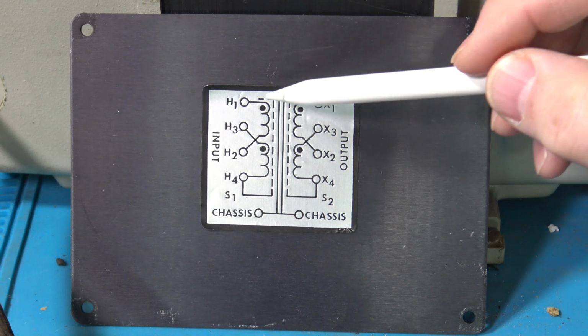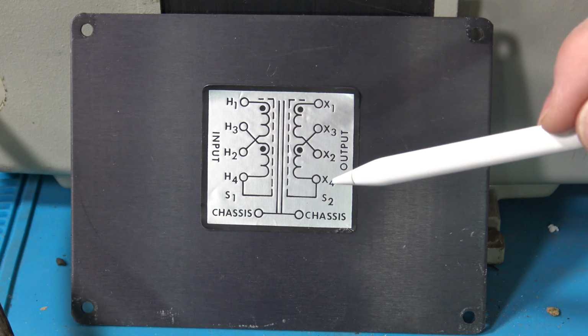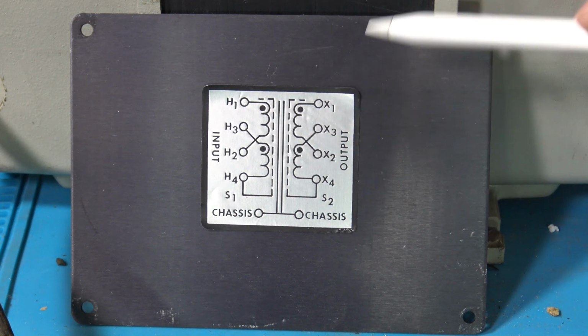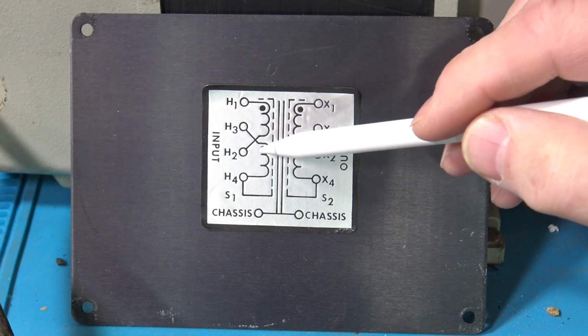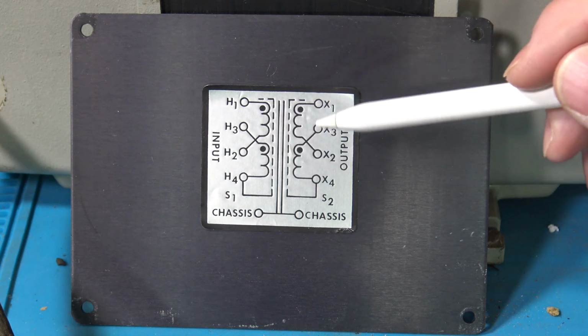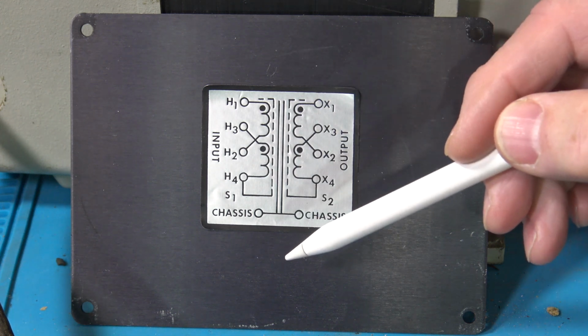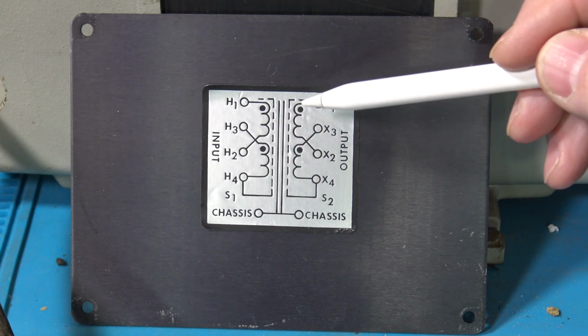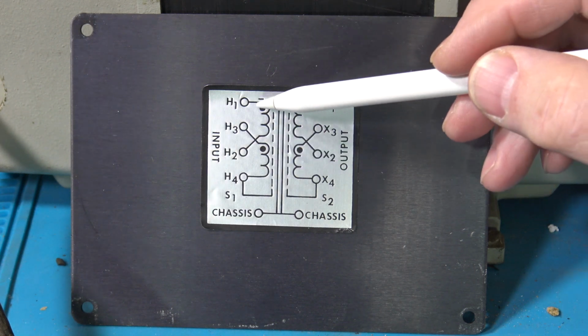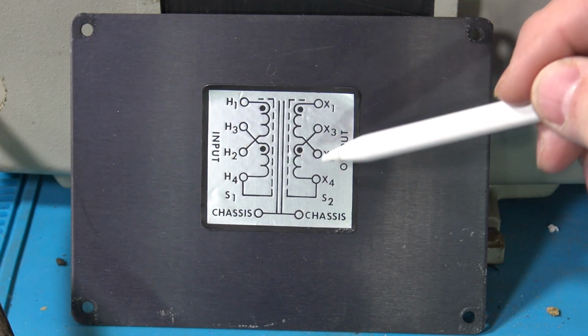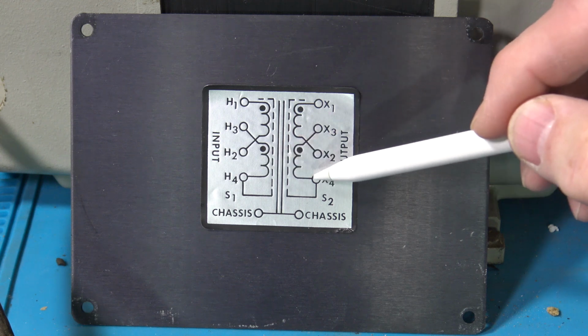Now, the only ones that were connected were H1, H2 for the input and X1, X2 for the output. So for some reason they didn't parallel these. Being in the States, since we're 120, you just parallel them. If it was 220 or 240, then you'd put them in series, but they weren't. These guys weren't connected at all.